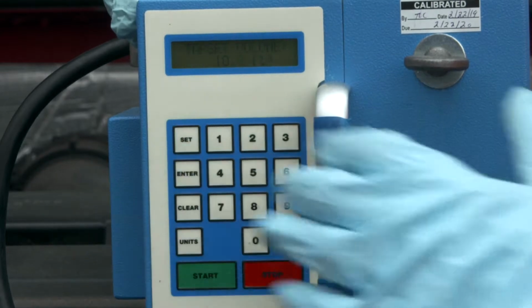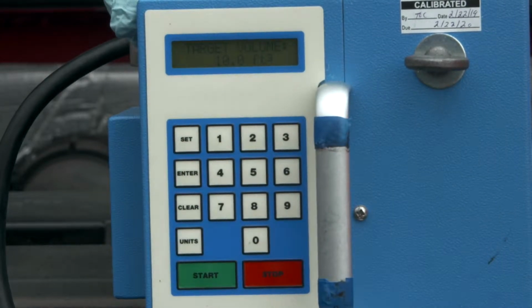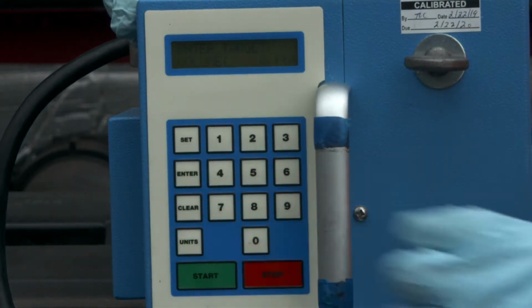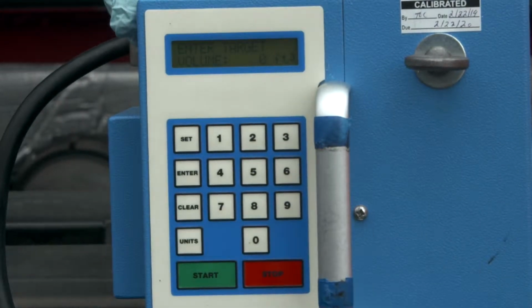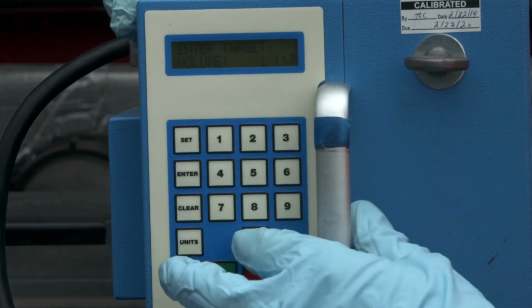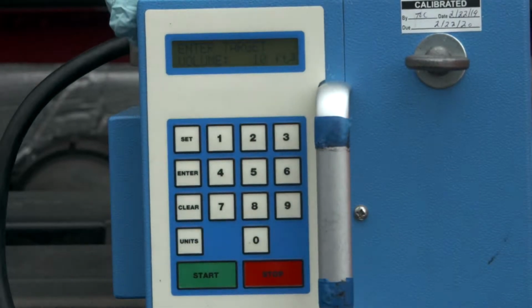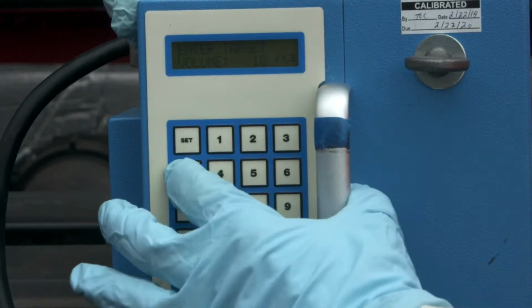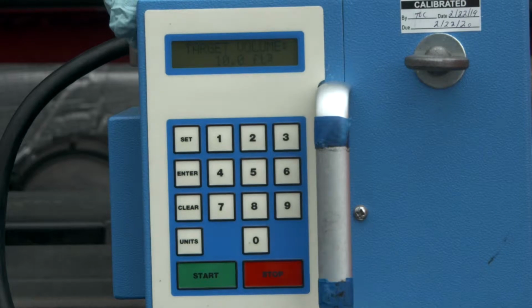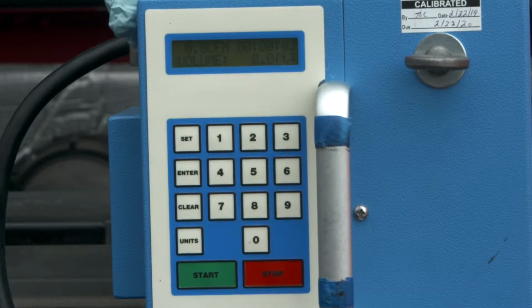Press the Set button found on the face of the air sampler. A default sample volume will be displayed. Press the Set button again and enter a sample volume of 10 cubic feet. Press Enter again, then press Start to begin the air sampler. To complete, it will run for about 10 minutes.